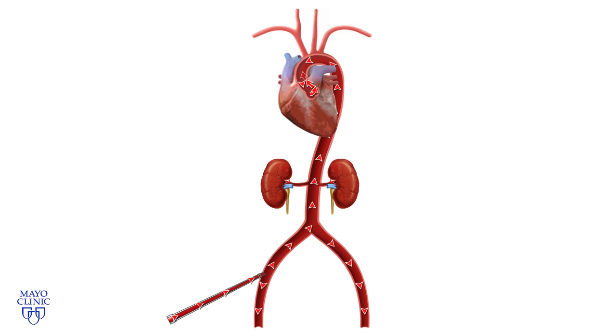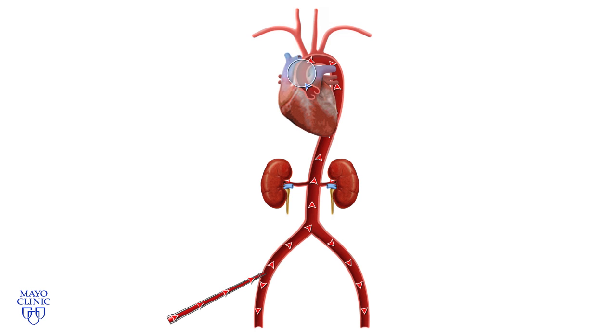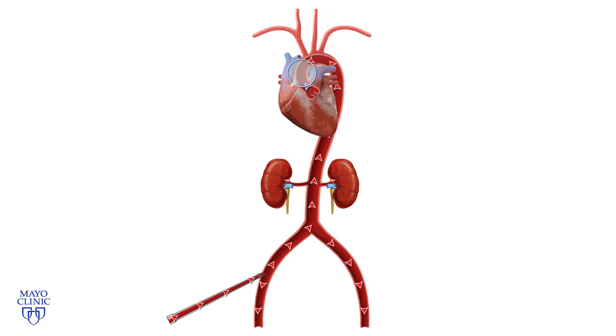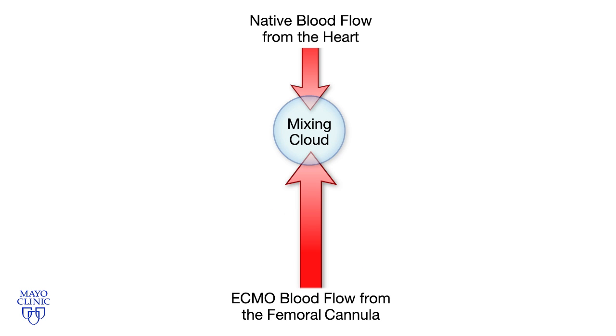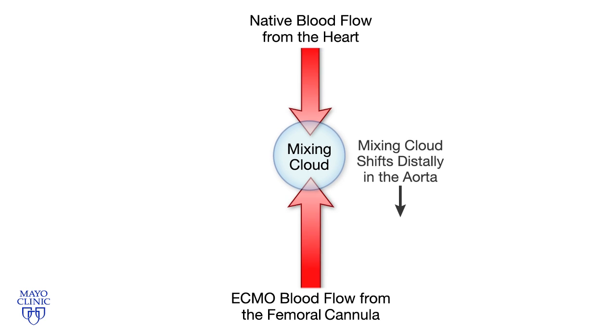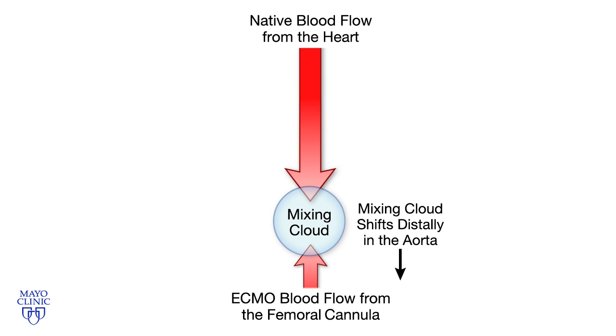Upon return of cardiac function, when the heart starts to beat and the aortic valve begins to open, the situation becomes quite unique. Because the peripherally placed ECMO cannula is pumping blood in a direction that is retrograde to the native blood flow, the two circulations merge or mix together in a location somewhere between the aortic valve and the arterial cannula. As left ventricular function is restored and contractility increases, the mixing cloud may shift distally in the aorta towards the arterial cannula. The same shift can occur if the ECMO blood flow is decreased.